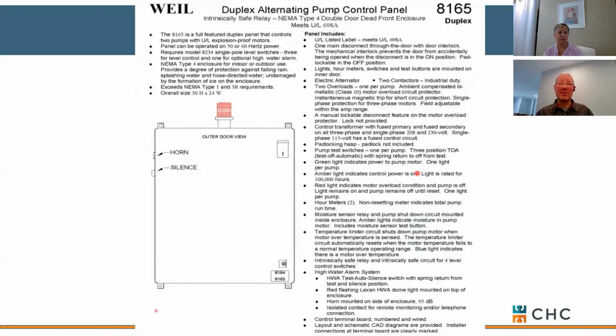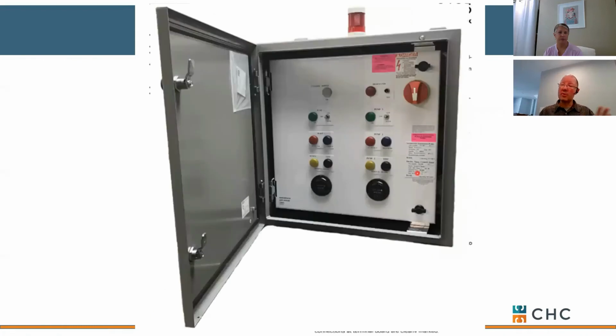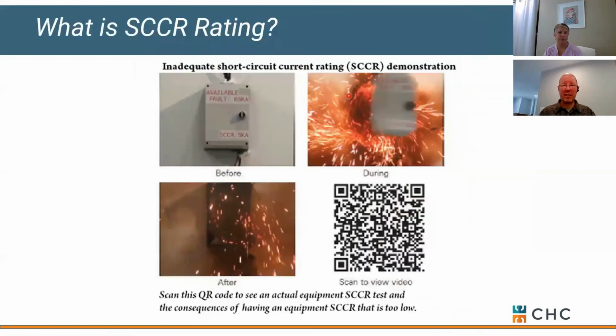Another thing that might come across your desk is something called double dead front, or a lockable control panel. If you're going into a public parking garage, you don't want somebody in there messing with all your controls, so you want the ability to lock that panel. That's all double dead front means: a lockable front panel. But once you open it up, you have access to all the controls hiding inside. You can order these as stainless if you want them outdoors. In a public space, you're probably looking at double dead front just for protection.